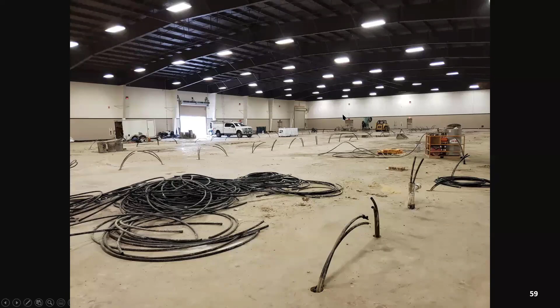Afterwards we trenched out most of the slab, removed it, and installed radiant throughout. Another picture of the same. In this case we were not allowed to drill through bedrock - St. Charles, Illinois has its own well, so they won't allow any bedrock penetration. So we stopped at bedrock, which is why we have so many holes. We're only 75 feet deep in each, but we do 4 in series, all 1-inch lines, and we now have 6 manifolds accessible in the floor that connect all of this.